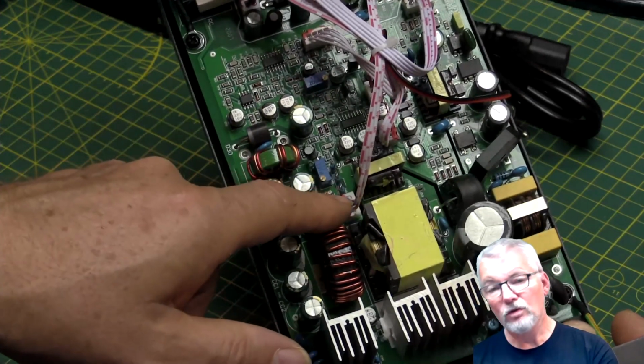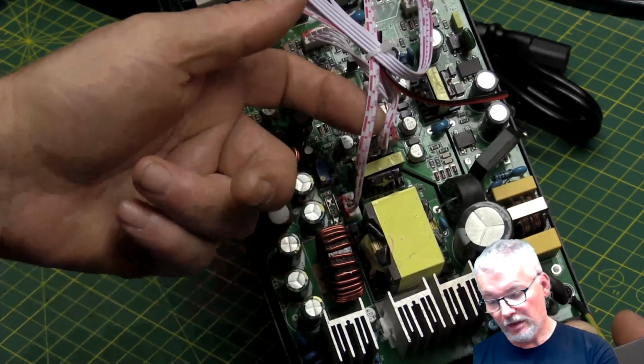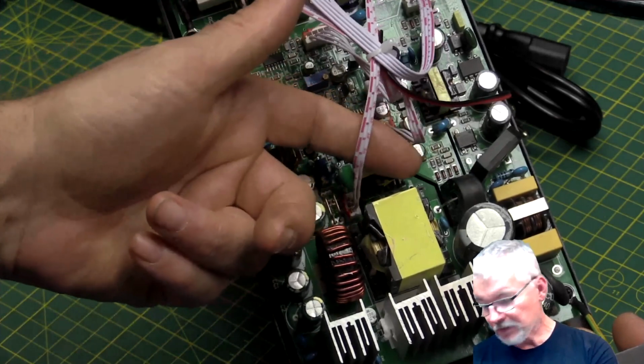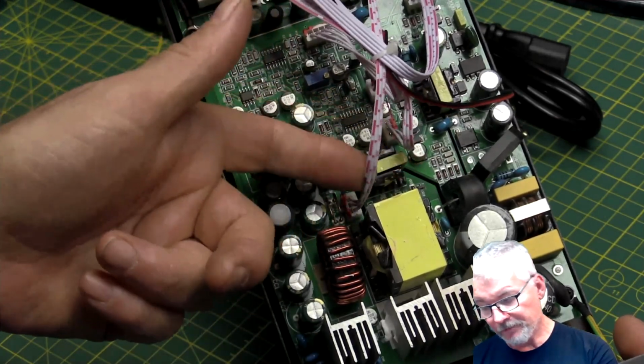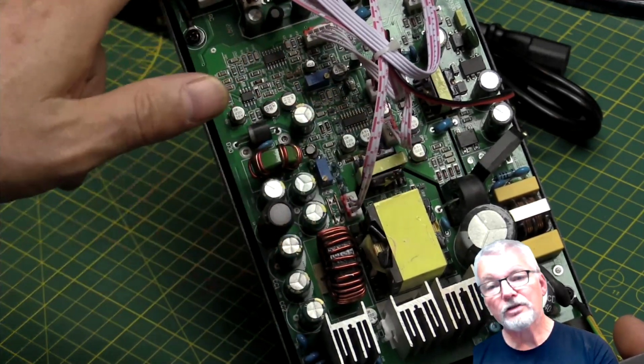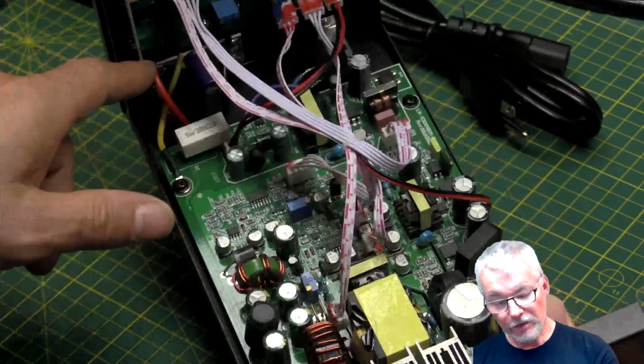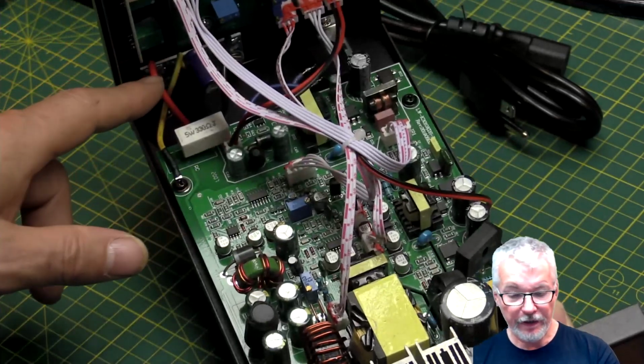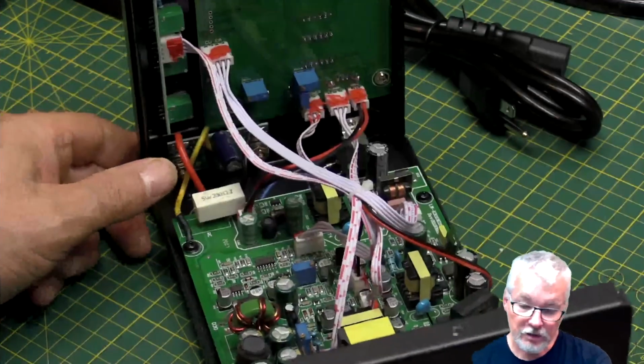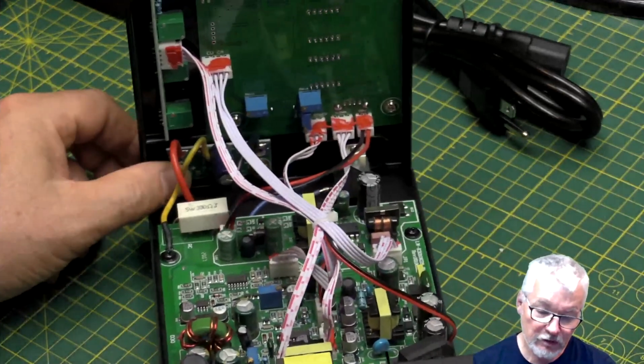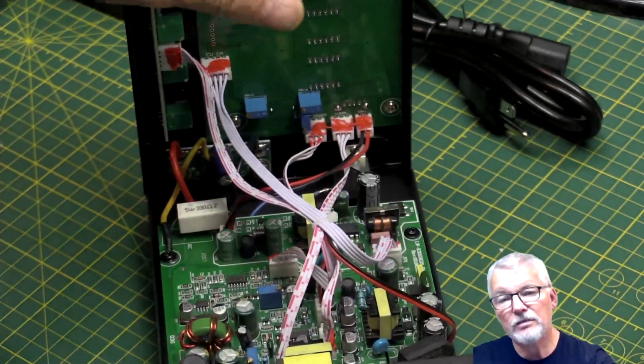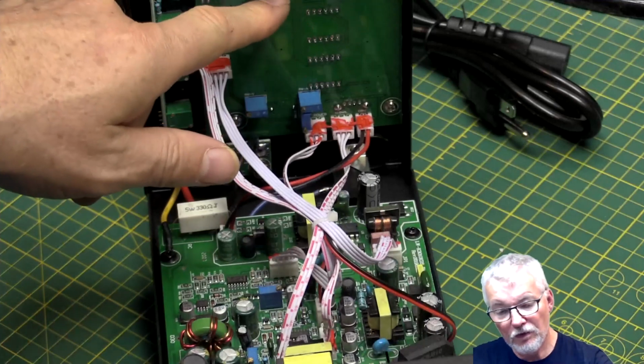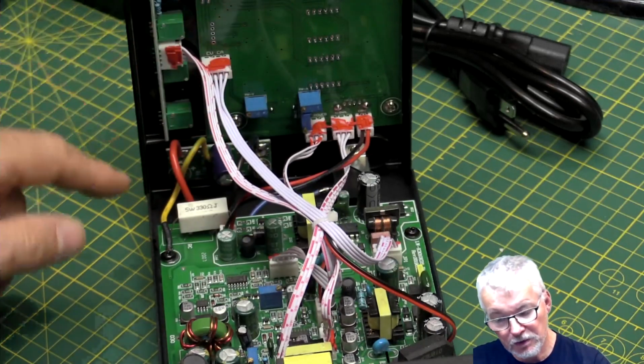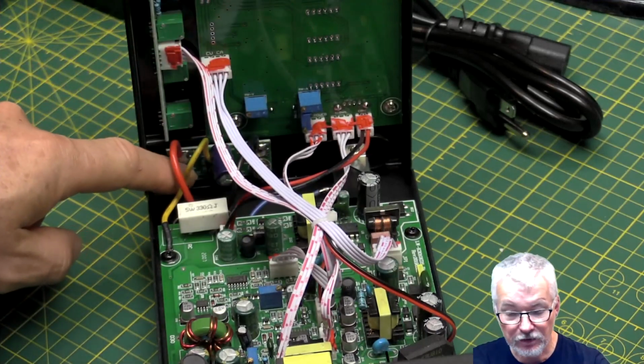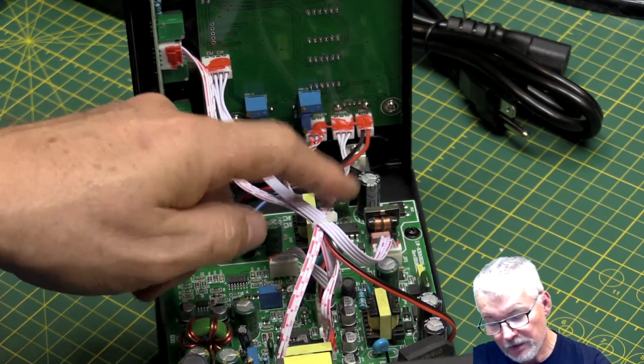in the board, on the board circuitry. It may be a tapped off signal from a control or something, but it's not measuring way up here at the output terminal. So that would account for why at high currents there's a significant discrepancy between what the display says for the output volts versus what the output is actually measuring. And that's because of where it's tapped off.